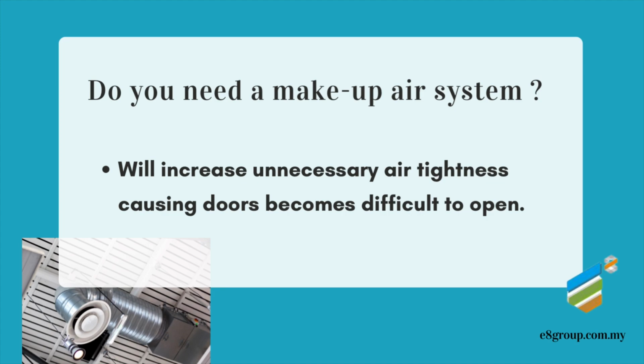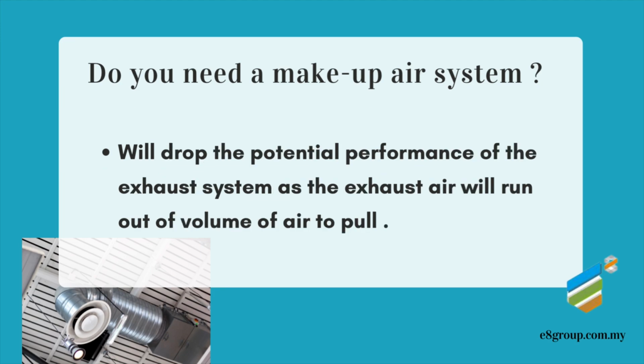The fan is designed to run at 5 kilowatts to generate 5000 CFM of air against 300, 400, or 500 Pascals of static pressure resistance. Now, you do not have makeup air. The moment you start, the fan pulls all the air out of the room, and after that it doesn't have any air.